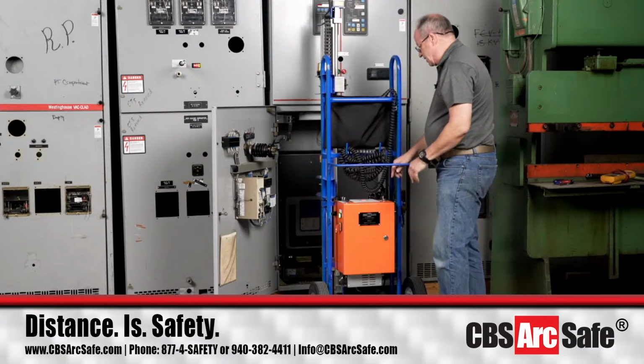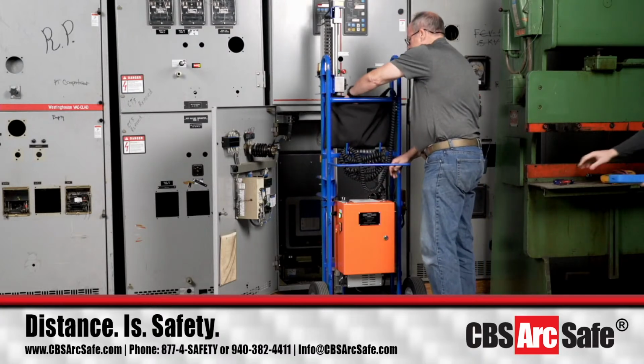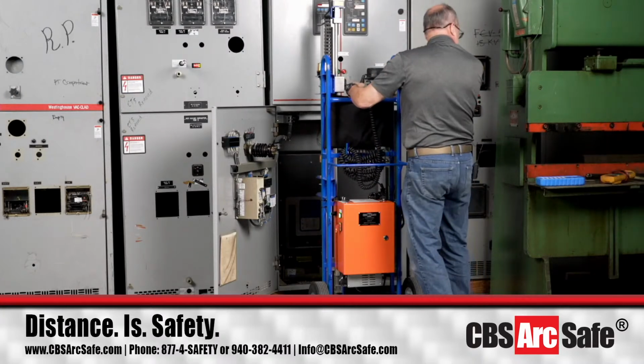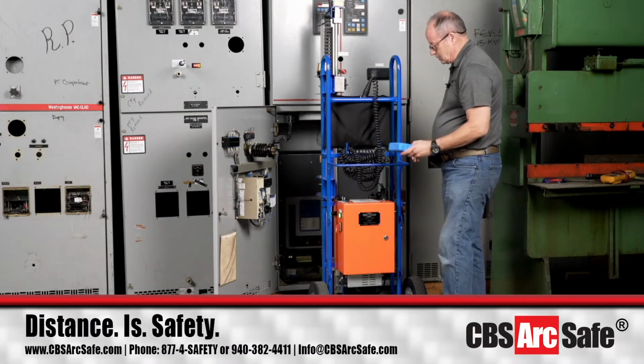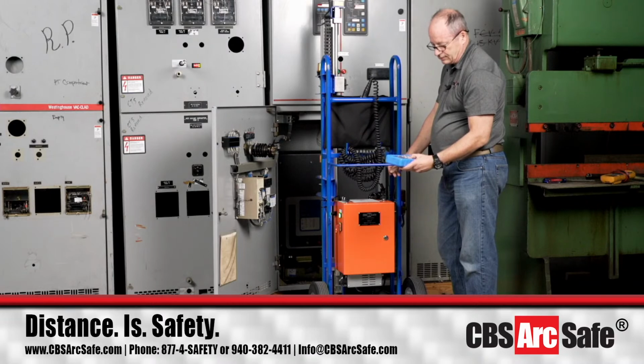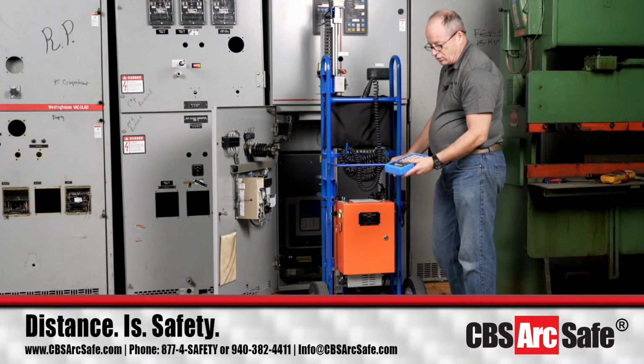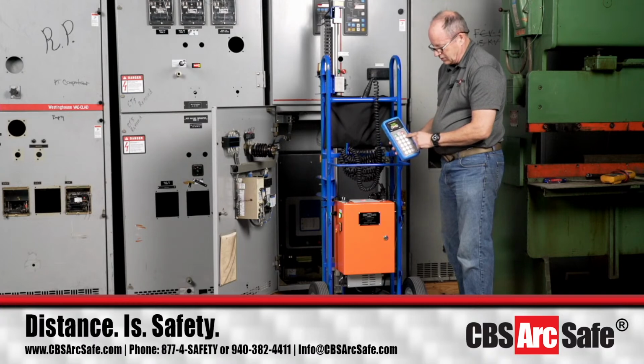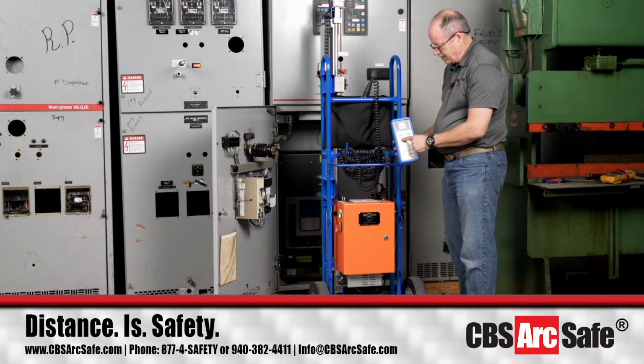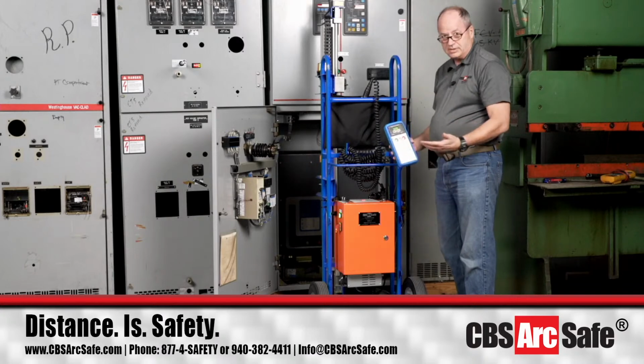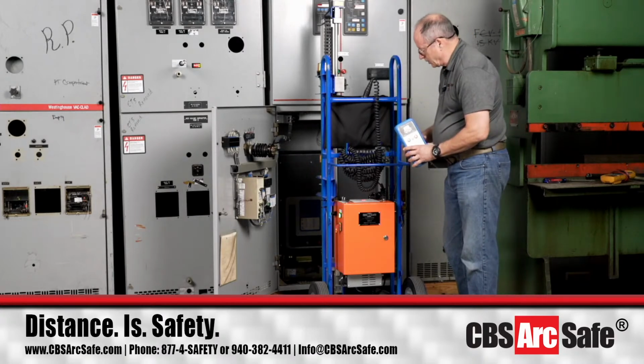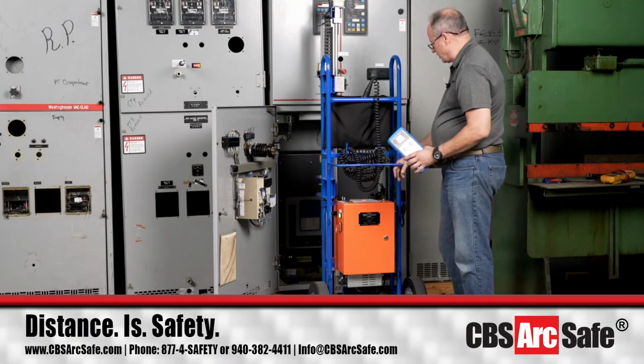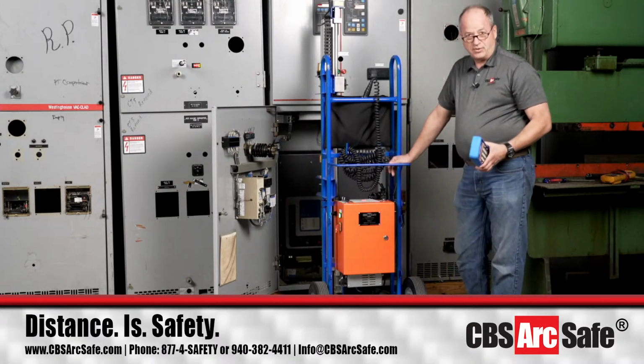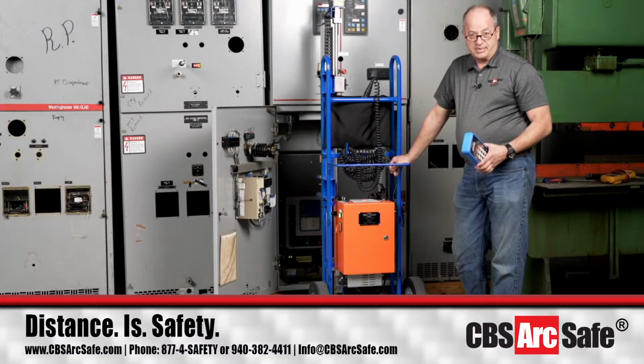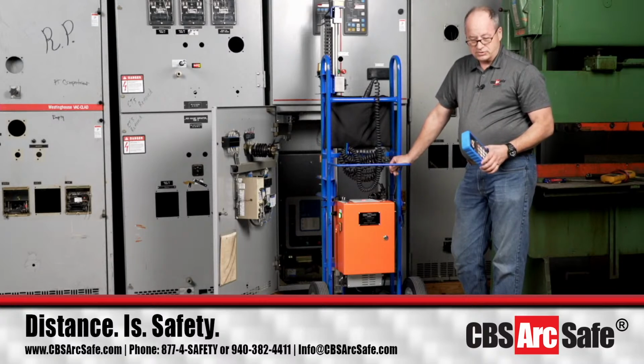With the unit set to 0 and using the radio remote, we will have the remove and install buttons right here. If I hold the button down, it's going to run. If I release it, it's going to stop. We're going to use our peak current button right here to help us record the peak current when we rack this breaker out, so that we can figure out how to set the unit to minimize the amount of force we use when we rack the circuit breaker.